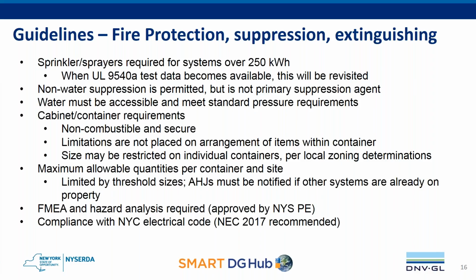For fire protection, suppression, and extinguishing, and as is required in the 9540 standards regardless, an FMEA needs to be conducted. And in general, there needs to be compliance with all standing New York City codes, including the New York City Electrical Code. We've noted here that NEC 2017 is recommended. Although NEC 2017 is not yet in force in New York City, it is the first of the NEC codes to directly address energy storage systems, and so it's recommended as a best practice.